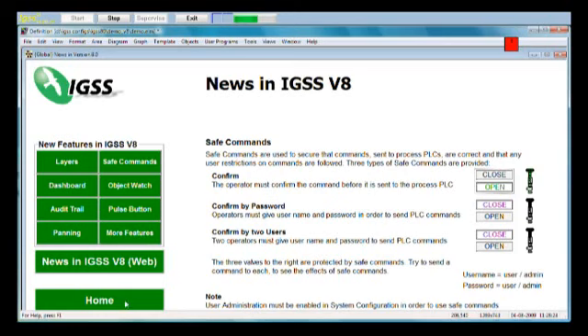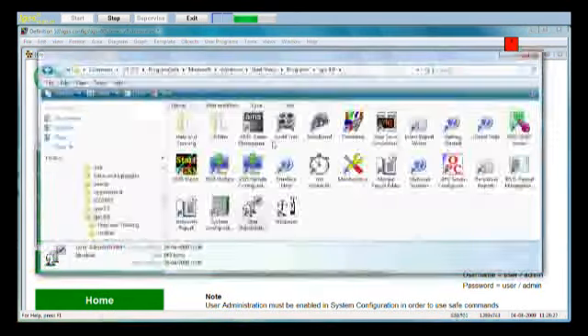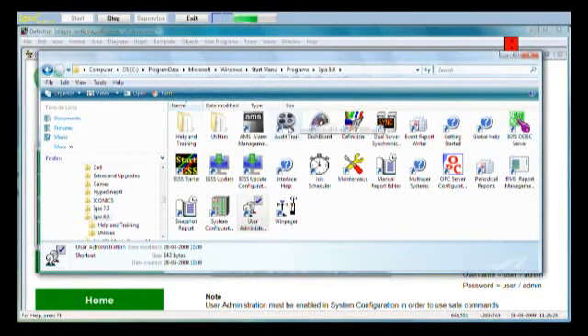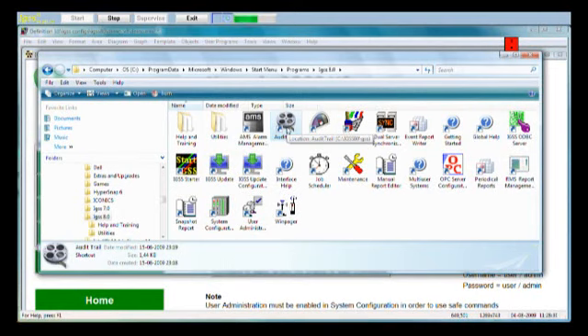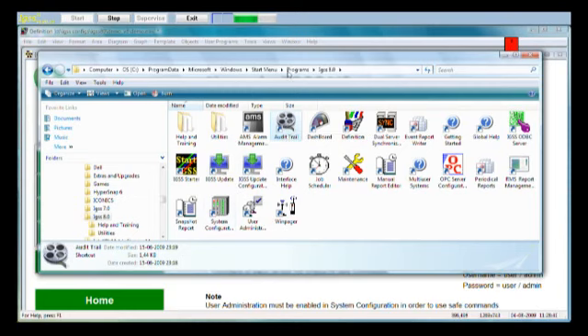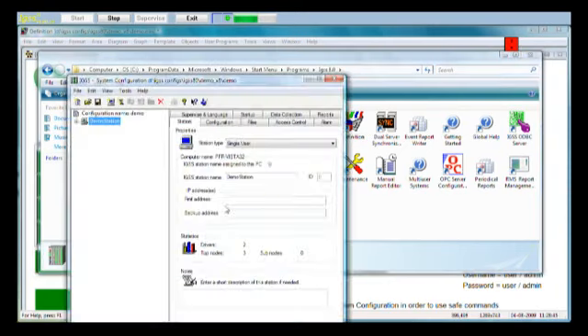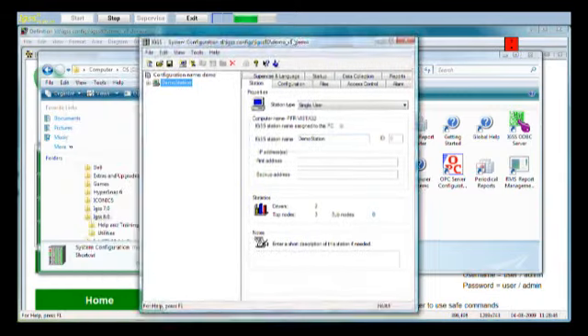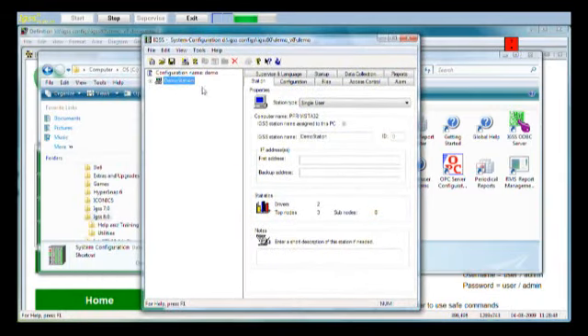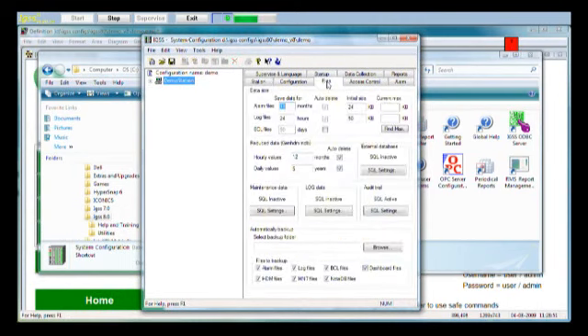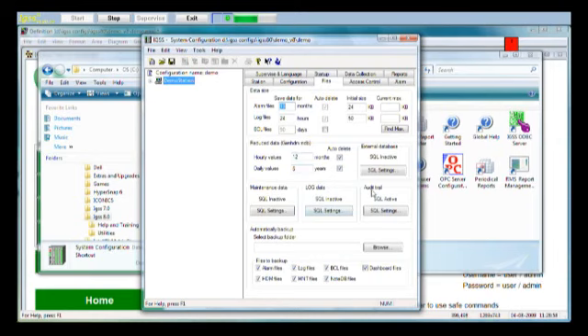An expansion of the security in IGSS and tracking is the new audit trail program. If you remember, we saw it in the start menu. Here it is. You can start it from here. You can also auto start audit trail together with IGSS, so when the user clicks the start button it automatically starts up. Now how do you set up the audit trail before you begin? You must go into the system configuration module, and in the system configuration module you should go to the files tab. Now on the files tab you'll find a new section called audit trail.